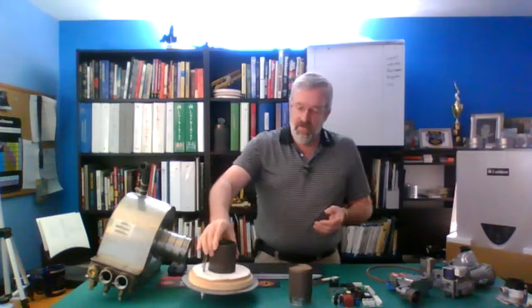A couple of things are important to understand. On all of them, I'm going to use a spark electrode with a built-in flame sensor. On KBNs, WHs, and KHBs, I have a secondary flame sensor. On a Noble, I don't. What it does is, I'm going to spark and light, and I'm going to sense flame here, and I use this as a backup flame sensor. An ignition cycle is something like this. I've got a 5-second trial for ignition, which is generally about 4 seconds of sparking. Within that fifth second, I prove flame. Once I do that, I'm going to go off into the modulation of the boiler.